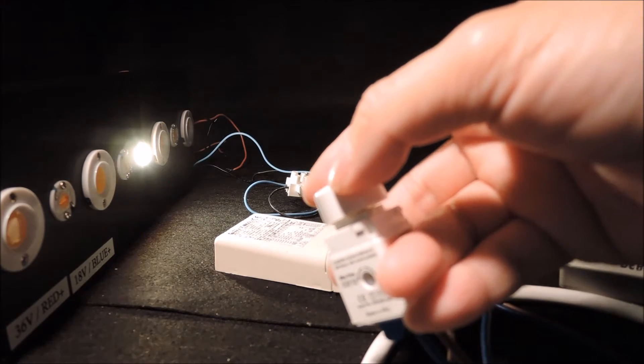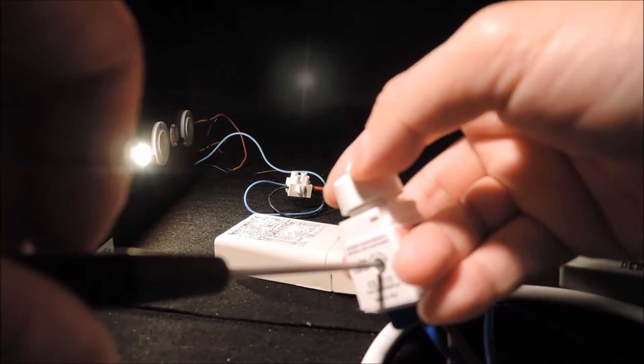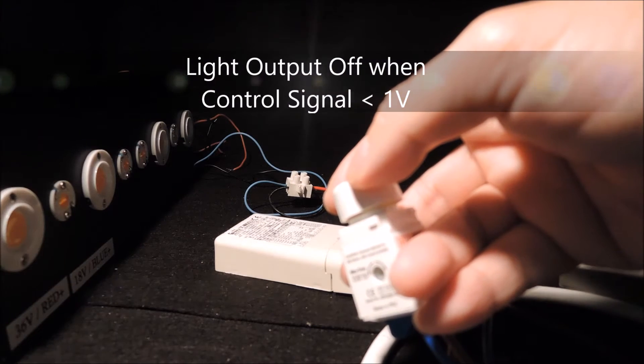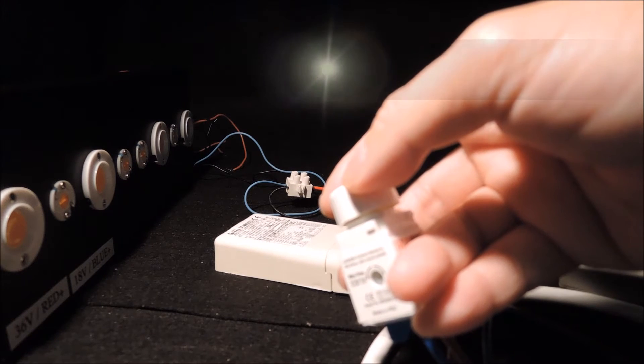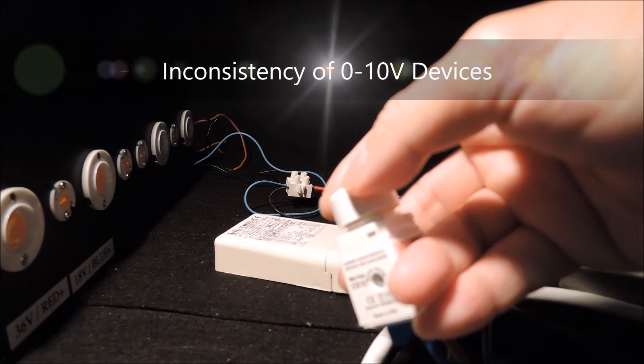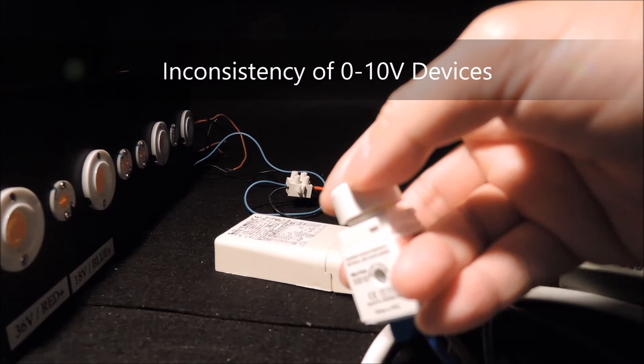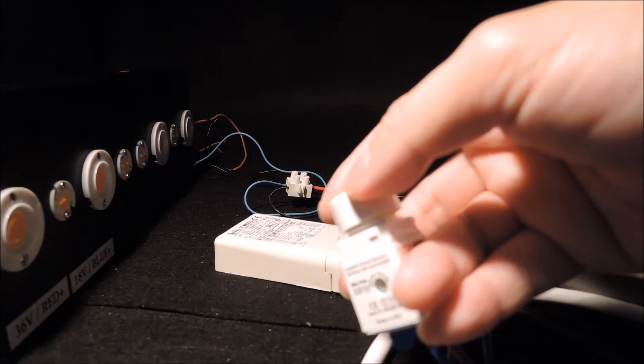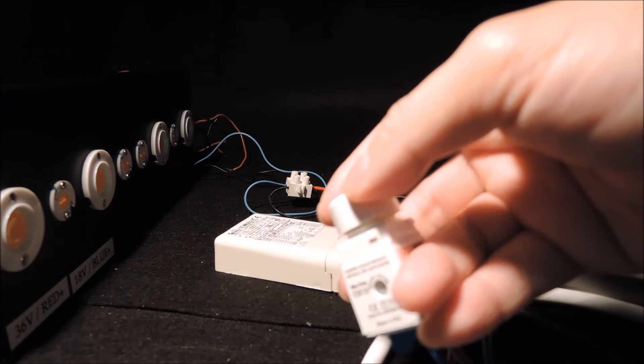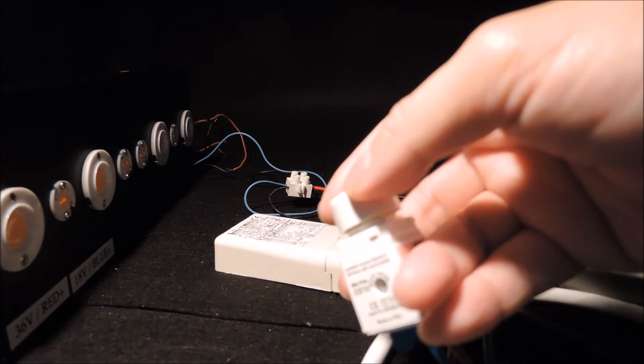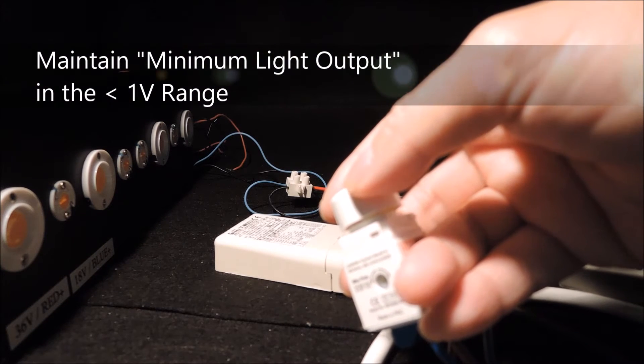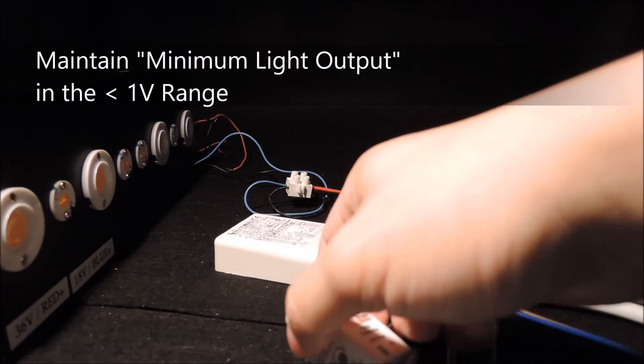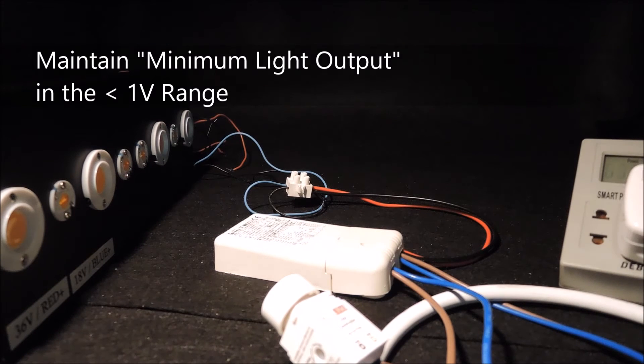If we continue to adjust the minimum trim downward, you'll see the driver actually switches off the light when the control signal hits below 1V. As a matter of fact, this is where you'll see the inconsistency of many 0 to 10V devices in the market. Some would have a bit of light, while some would switch off the light output as we've shown in this case. This is because there is not a clear definition for the less than 1V region. In this region, the driver should maintain a minimum light output which is largely up to the manufacturer's own interpretation.